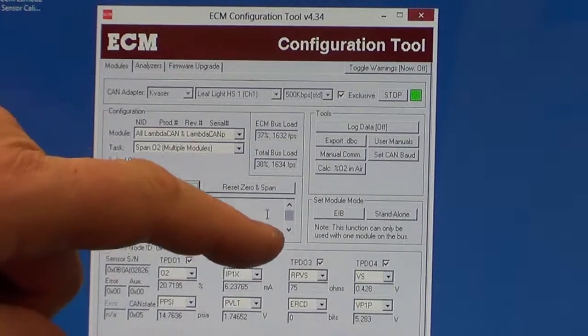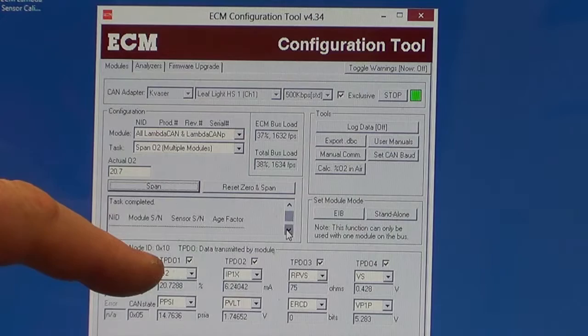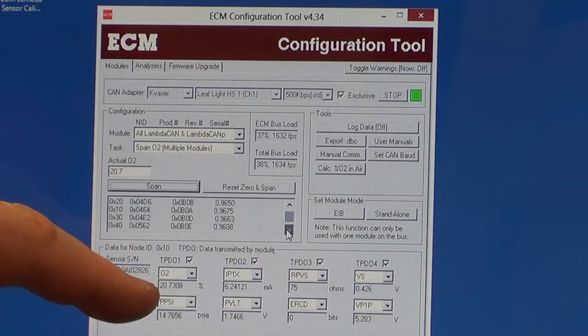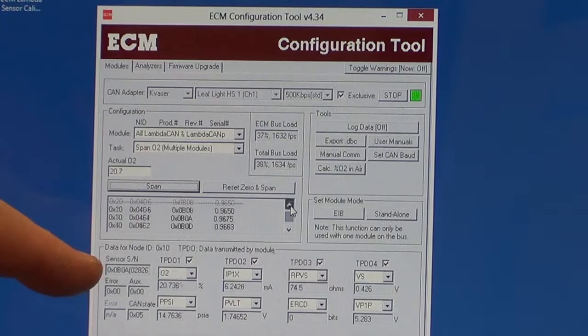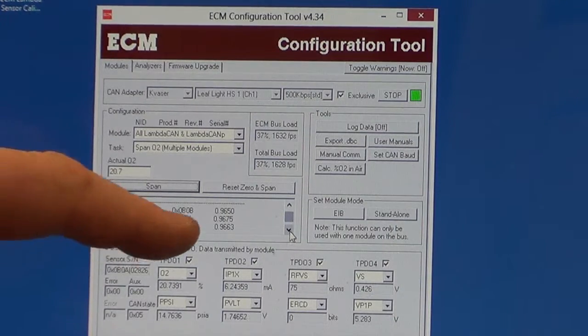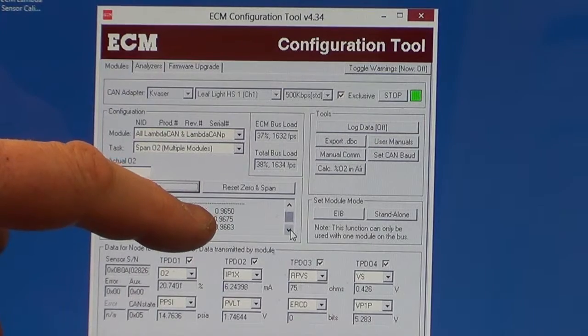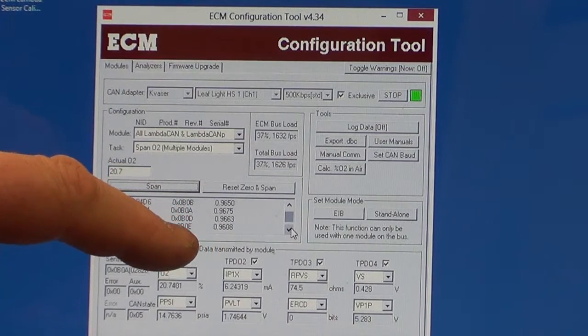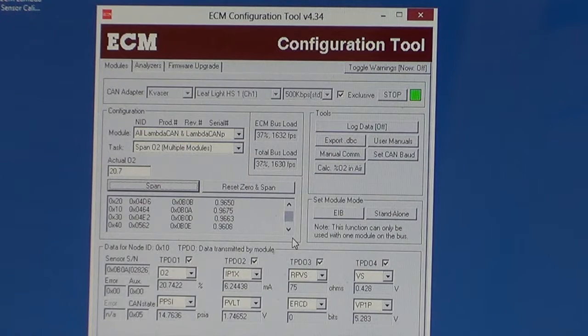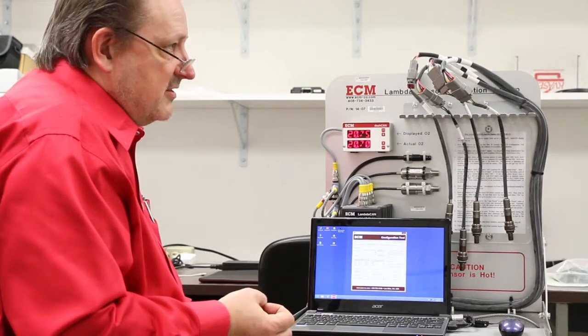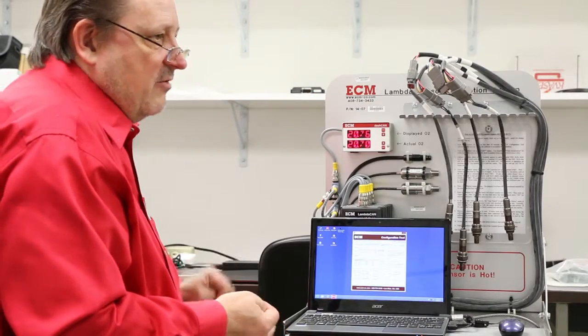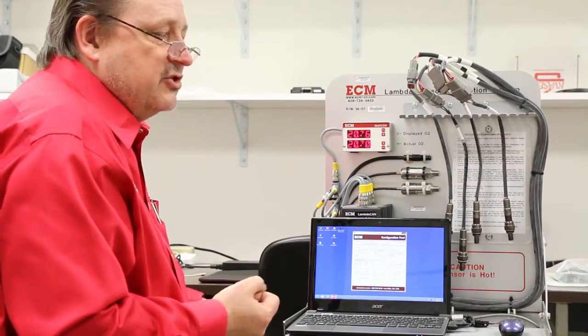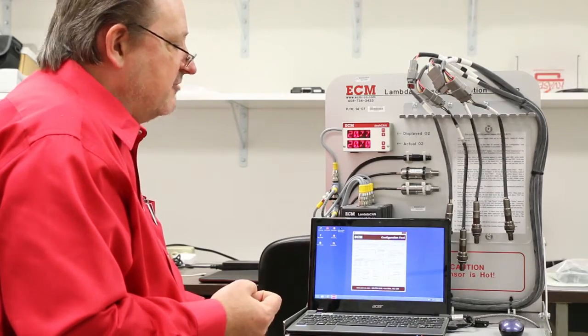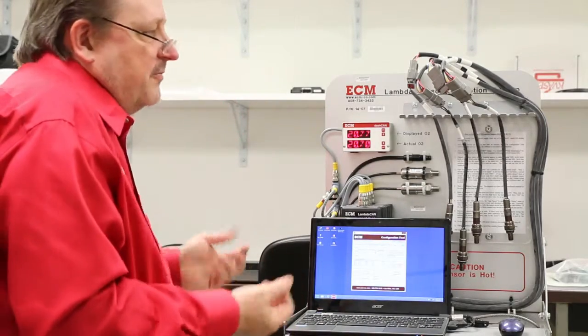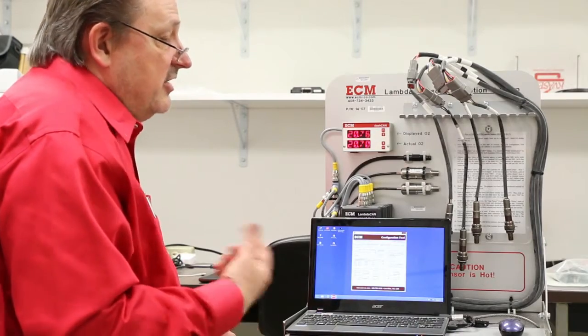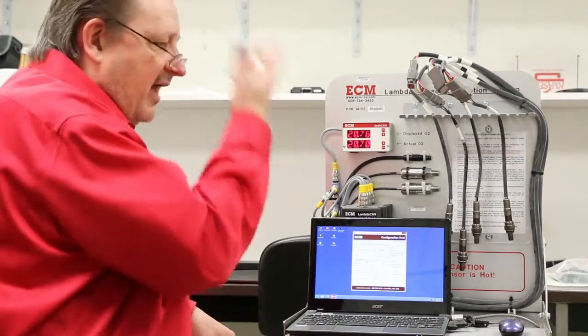Also, you can roll down in this and look at the age factors for the sensors. That's the numbers here. See 0.96, 0.96, 0.96, 0.96. When the sensor is brand new and it's been calibrated by us, and you hang it in air for 1 hour, it's going to be very close to an age factor of 1, which is like brand new, like 100%. As the sensor ages and you do the calibration, the number will go down, 0.96.